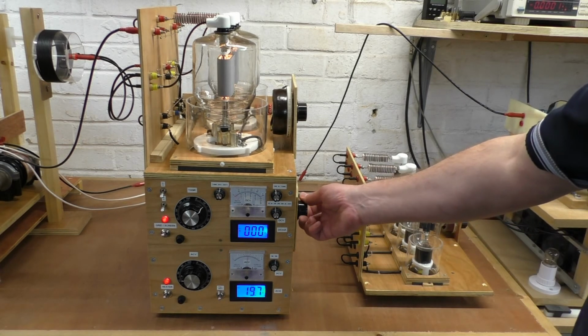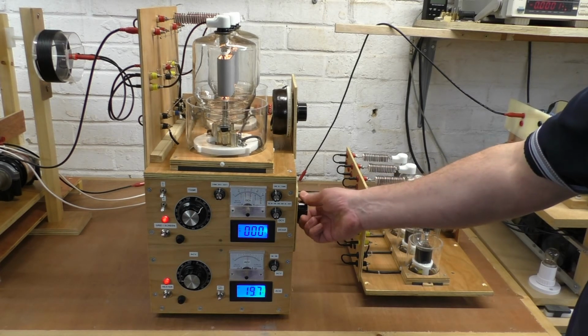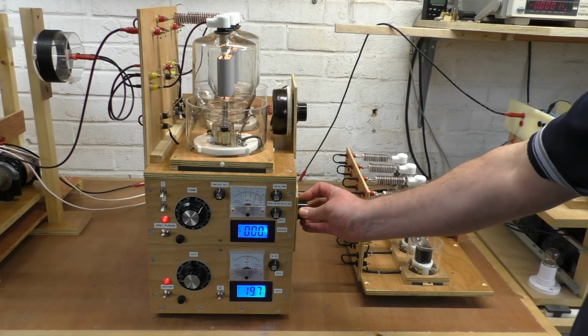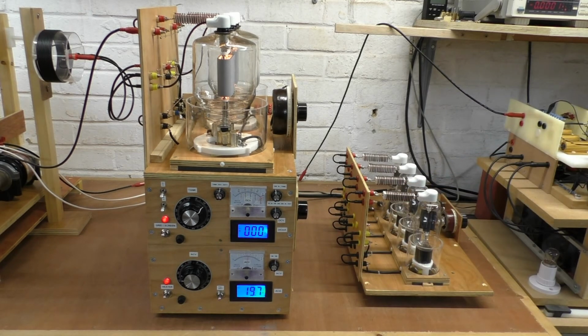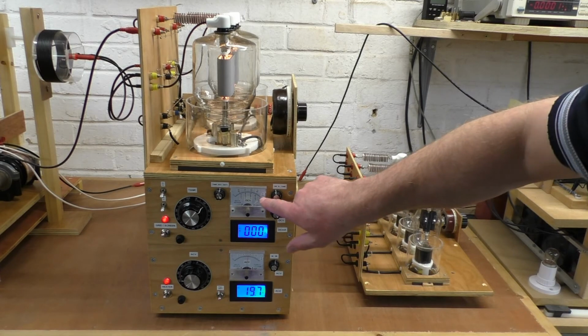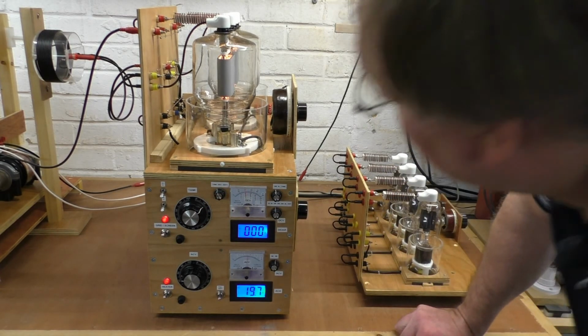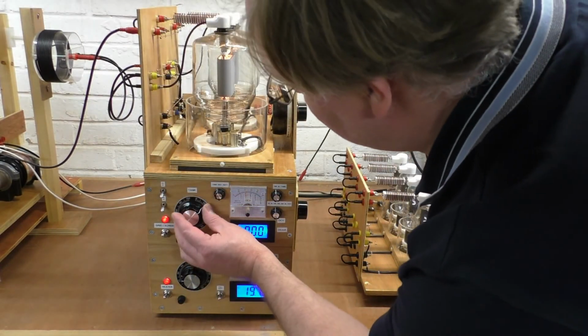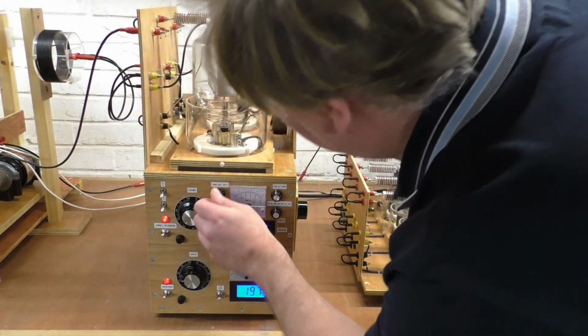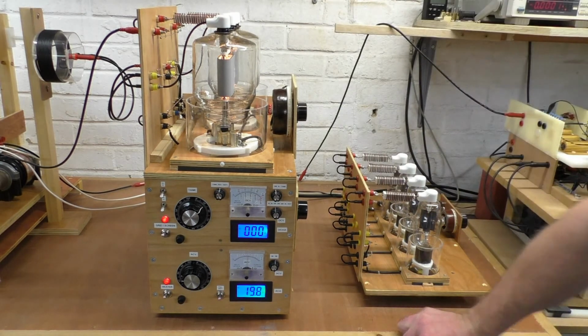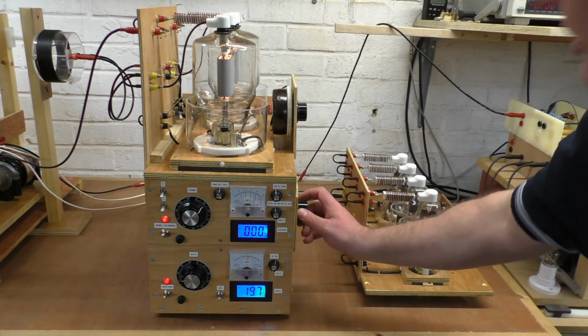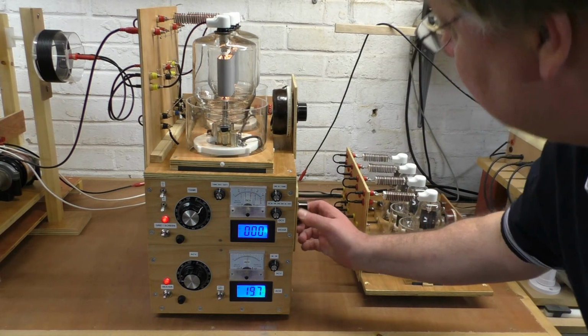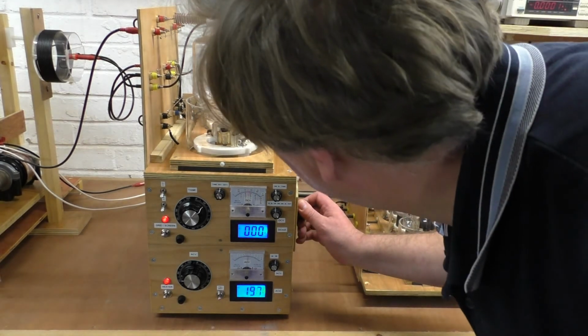So if I bias it all the way down to its lowest point, we get just a tad over minus 100. Going back to the tank, it's sitting just a tad over 200. So if I bias that back out, it's minus 100 volts. But if I want to set minus 50, now with the tank set, I can set it there.